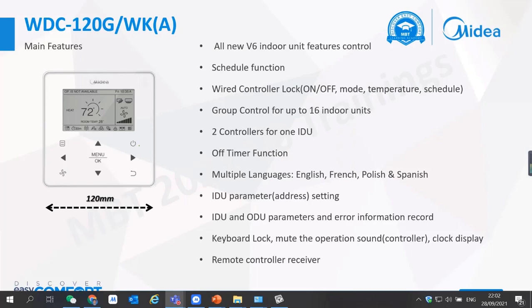So usually in a big office, you may have a central controller for a schedule so units automatically turn on and off. But you've also installed wired controllers. Suppose I'm working overtime today, so I use this wired controller to start the air conditioner, and I've already set after-hours. So after 4 hours, the indoor unit will automatically shut down. This is the after-hours or off-timer function.